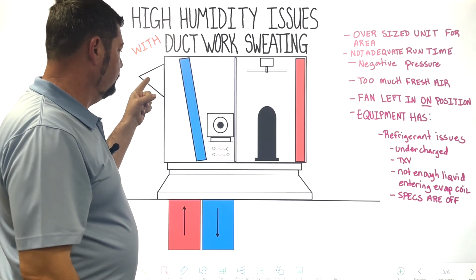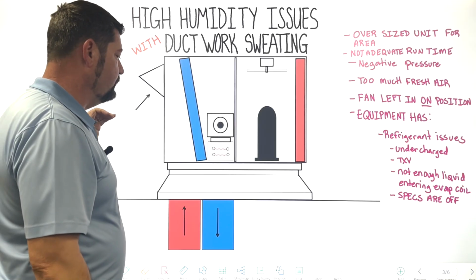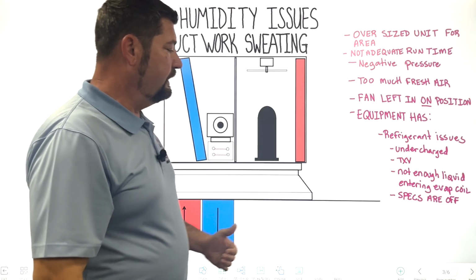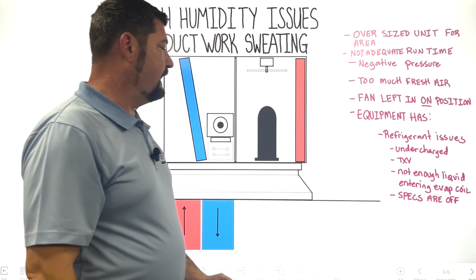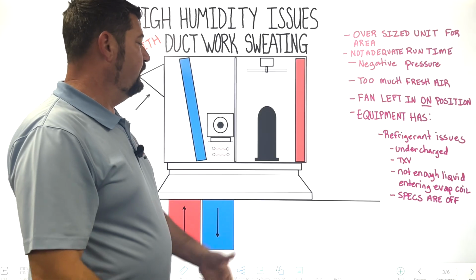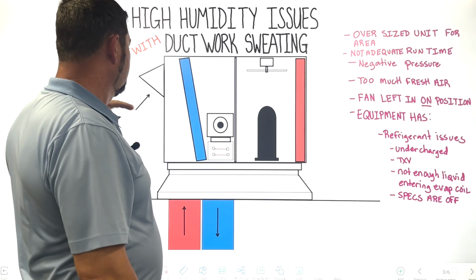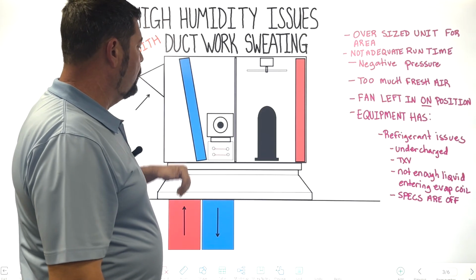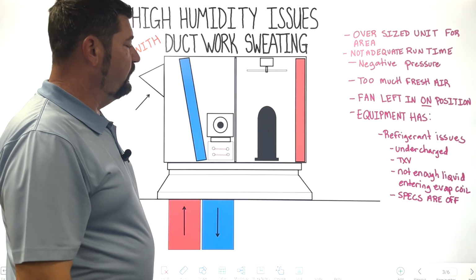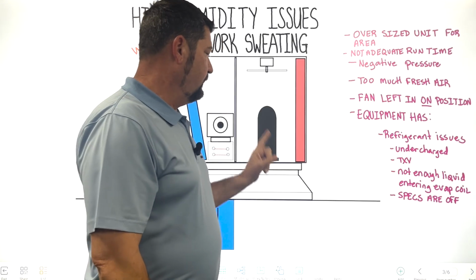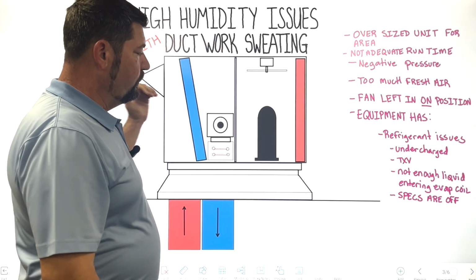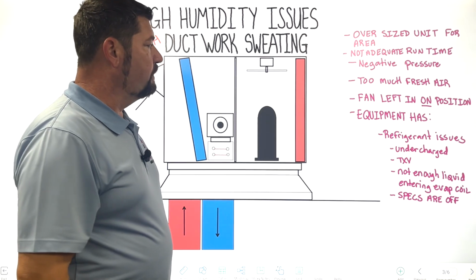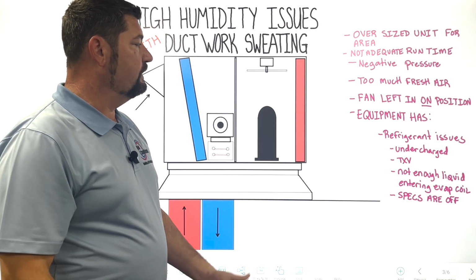It's like these fresh air dampers are there to stop intrusion of humidity coming in naturally and force any humidity being added through a cold coil. But the moment we leave these fans in the on position and we cycle that compressor off, we create a second problem that was induced by just operation error.